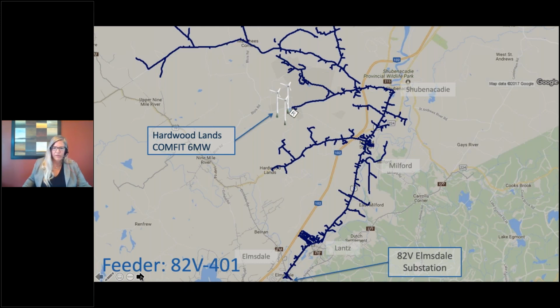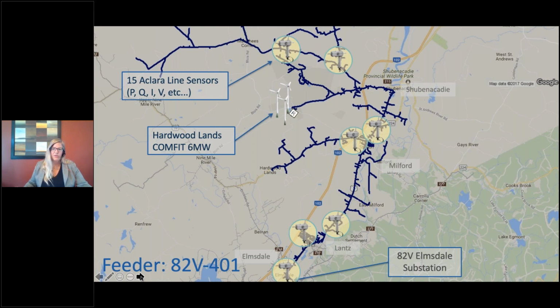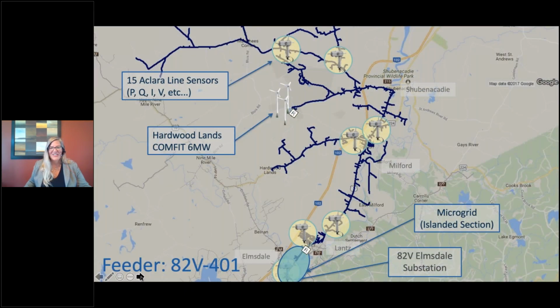The next image shows how much of the feeder the battery would support, and you can see it's not much. The sectionalizing recloser is just upgradient of a sportsplex that has 2 ice pads and a blow-up soccer dome, so that load was limiting how far we could build our microgrid. But we can support about 300 homes. The power pack has a 2-hour peak duration, but in the summer, if we had to action the microgrid, the load's light enough that we could provide backup power for that whole section for much longer.